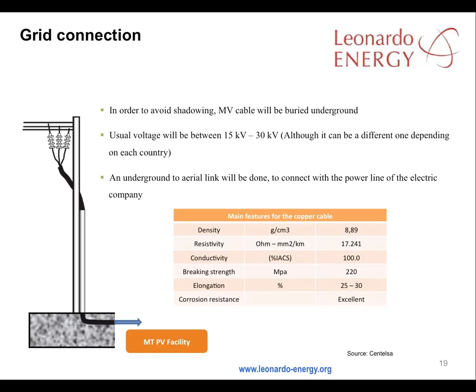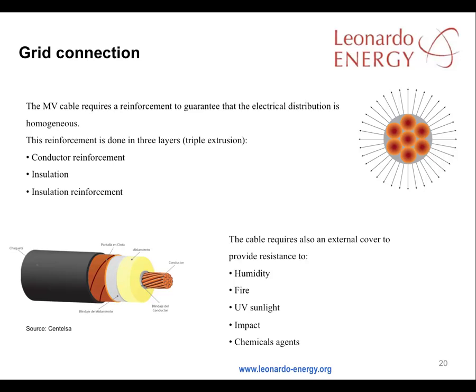An underground to aerial link can be made to connect the plant to the electricity company's power lines. The medium voltage cable requires reinforcement to guarantee that the electrical distribution is homogenous. The reinforcement is in three layers: conductor reinforcement, insulation, and insulation reinforcement. The cable also requires an external cover to provide resistance against humidity, fire, ultraviolet, sunlight impacts, and chemical agents.